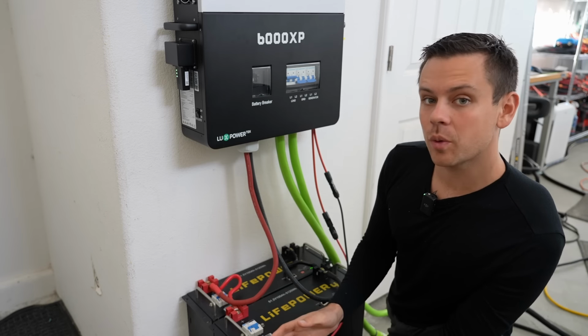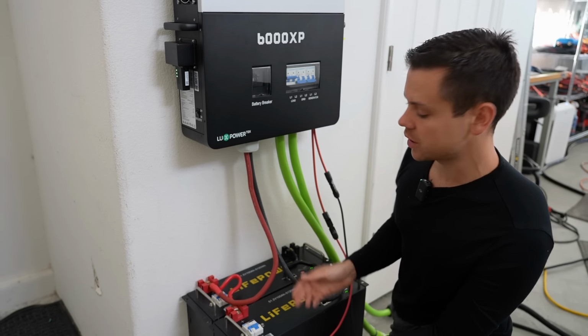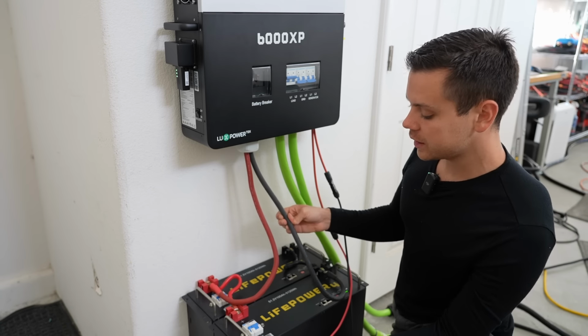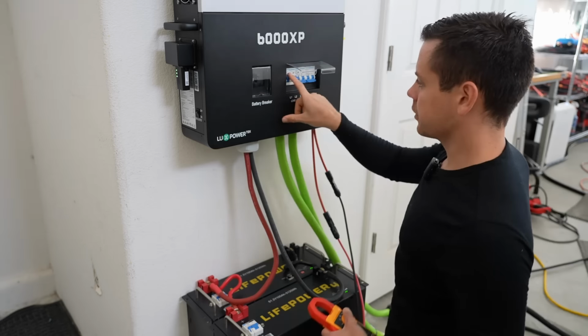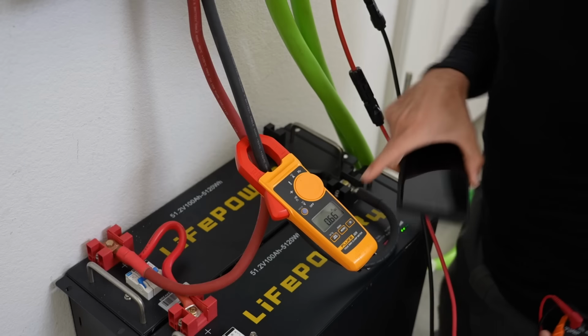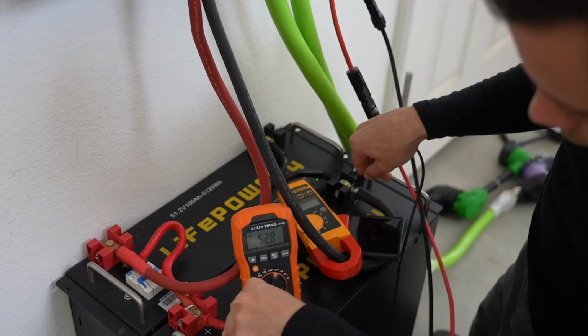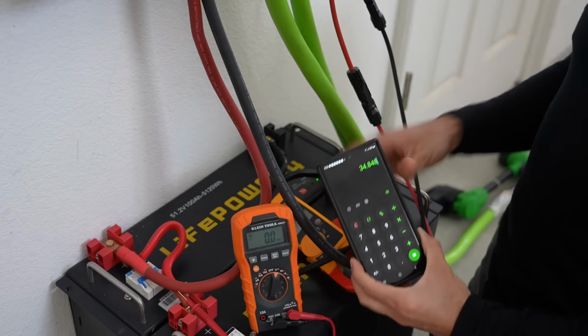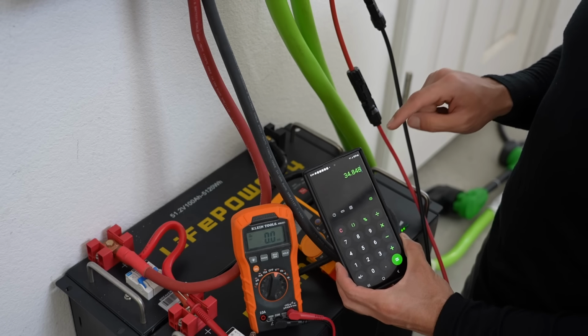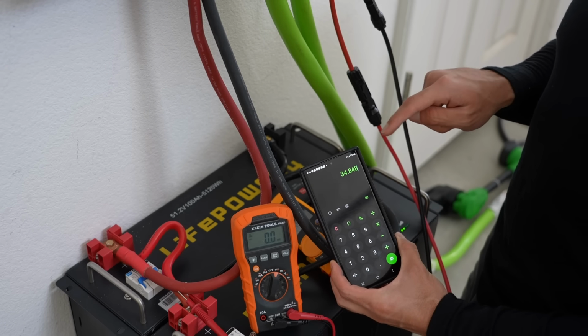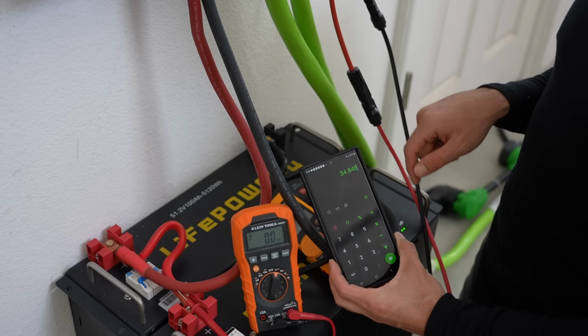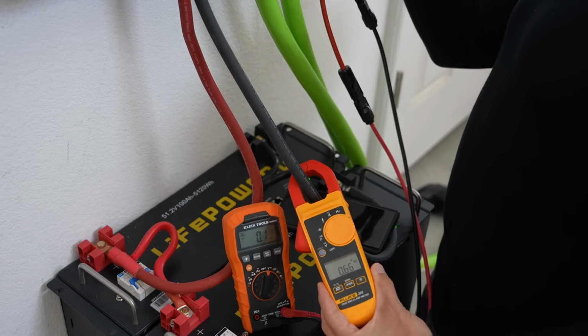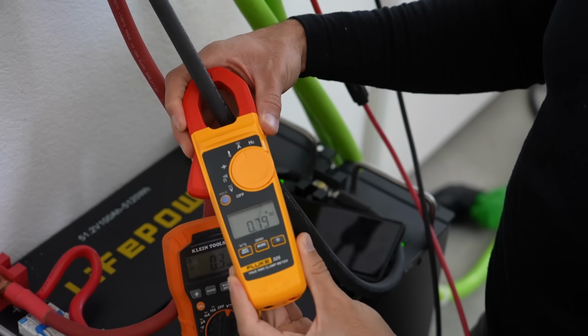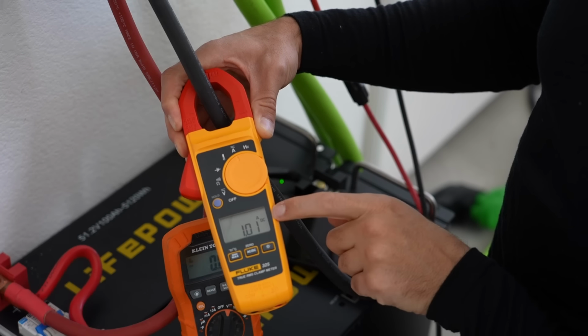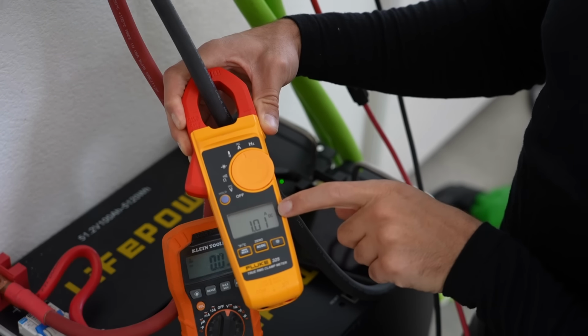Now the first thing we want to test is the idle consumption. We're going to turn the inverter on and see how much power it draws. First we're going to turn off the output. We're getting 0.66 amps at 52.8 volts, and that's 34 watts, so that means it's in eco mode. I'm going to turn the inverter off and back on again, and it should go up to 50 watts. Now it just switched on, and we are at 1 amp, so it's pulling 50 watts.